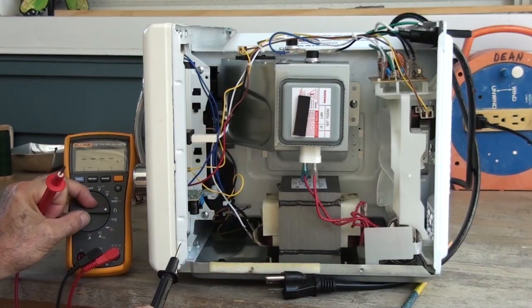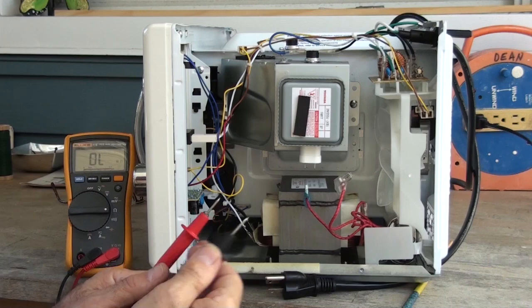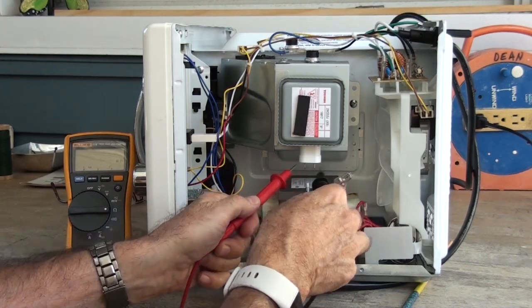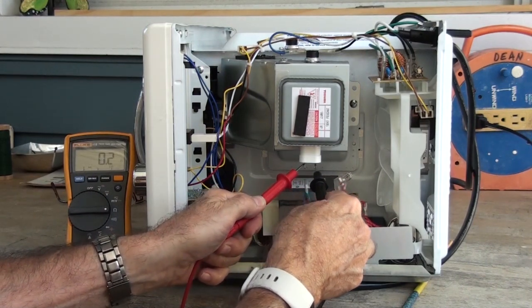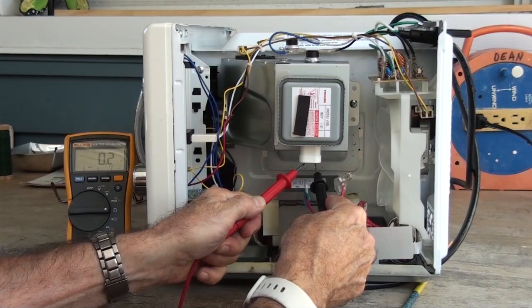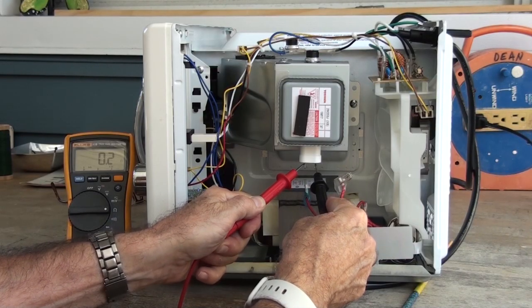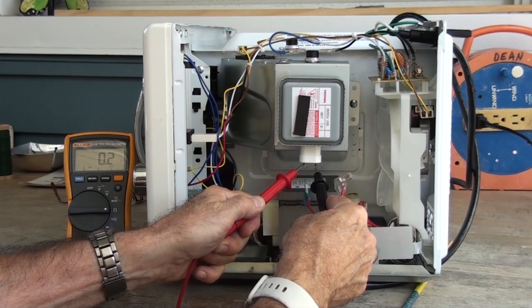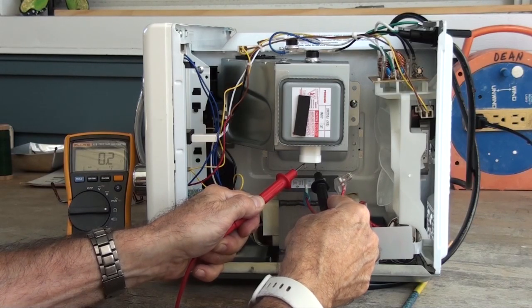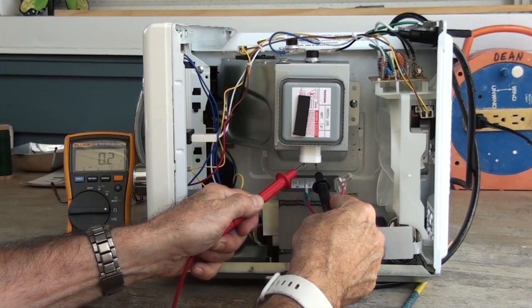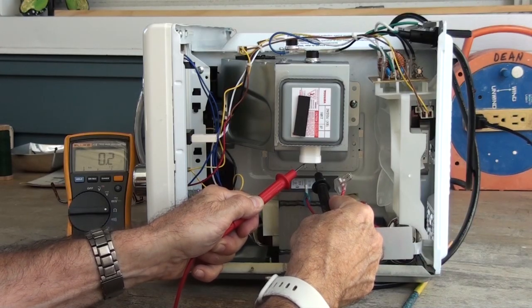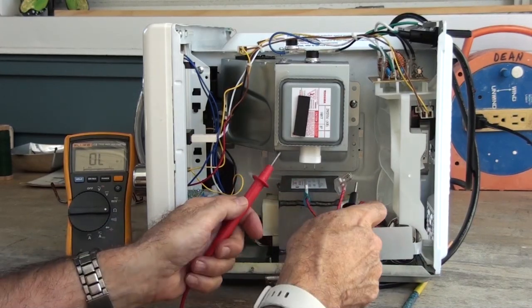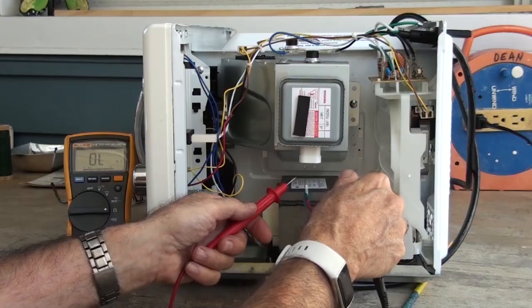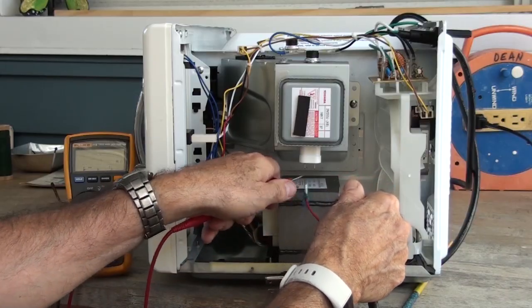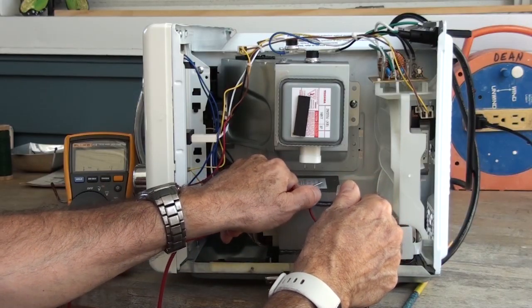I'm going to put this on the ohms range. All right. And we're going to check resistance across the windings, and sure enough, it's reading 0.2 ohms, which is virtually shorted, which is what it should be. The filament winding is a piece of metal inside that heats up, and that should be a very low resistance. And just to be sure, we can also check the resistance through the filament winding of the transformer, which should also be low, because it's powering a high current at a low voltage.